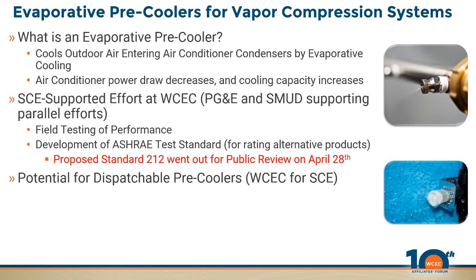So the new thing here is there's a big concern about the duck curve and issues with controlling the grid. One thing we've been doing on the current project for SCE is looking at the potential for dispatchable pre-coolers. In the past, there were programs where the utility would pay you per month for the right to turn off your air conditioner. The idea here is that instead of turning off your air conditioner, they'd simply send a signal that turns on the water on your evaporative pre-cooler.